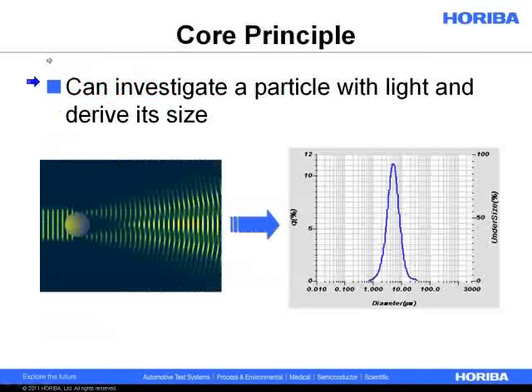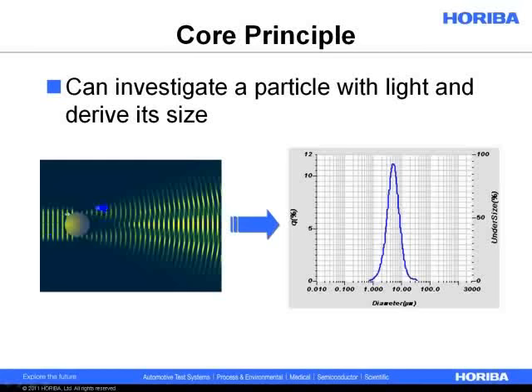Here's the core principle. If anyone ever challenges you, how does this big box work, it basically comes down to: we can investigate a particle with light and derive its size. If we consider this to be an ideal point scatterer, we're hitting it with some well-behaved column of light, and the light is hitting it on the edge. This is called edge diffraction. It's creating waves, and somehow we can study the overlapping interference pattern and derive a particle size distribution from it. This is the very core principle.